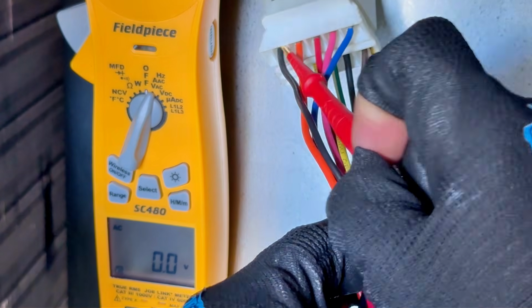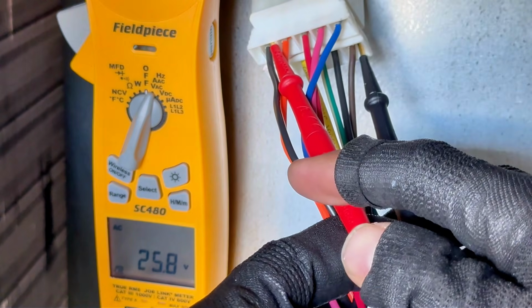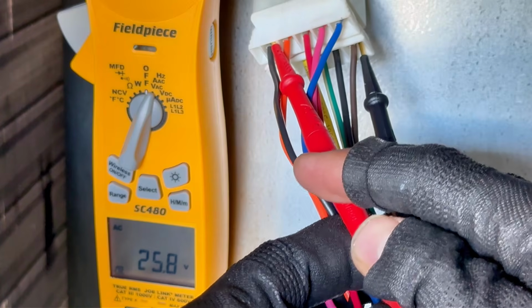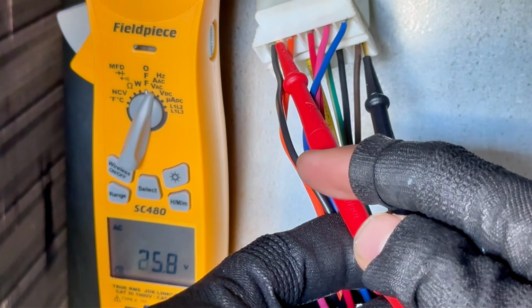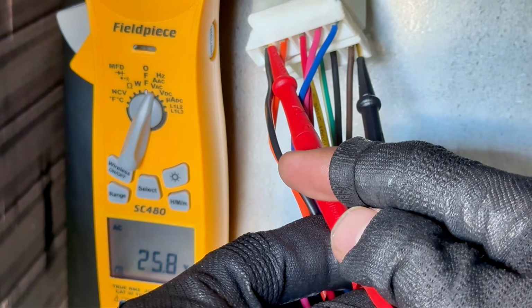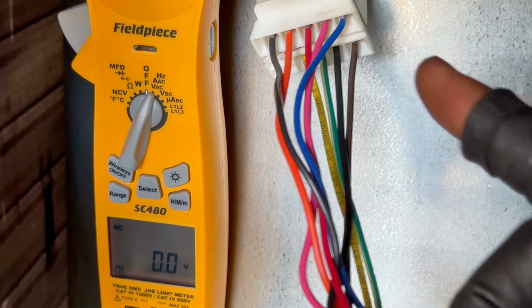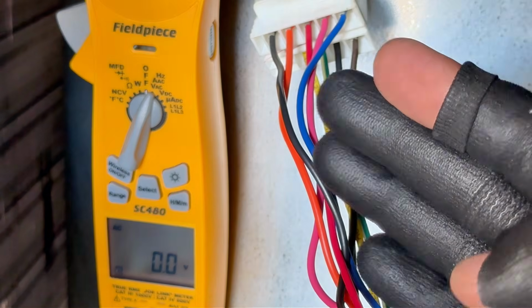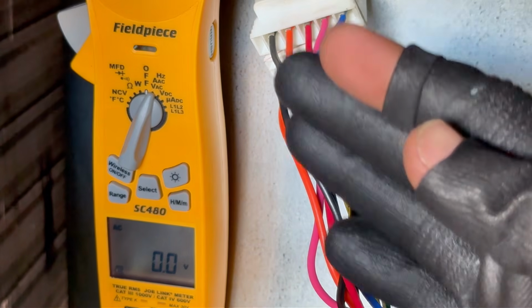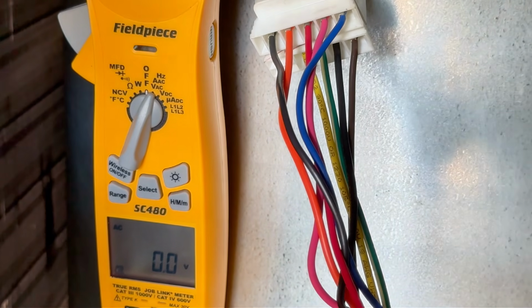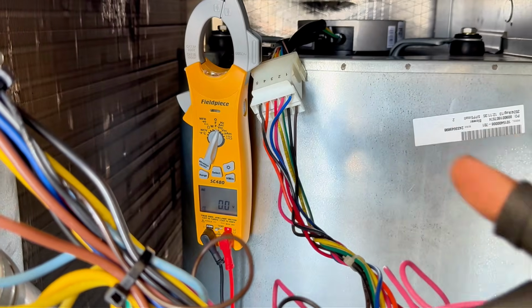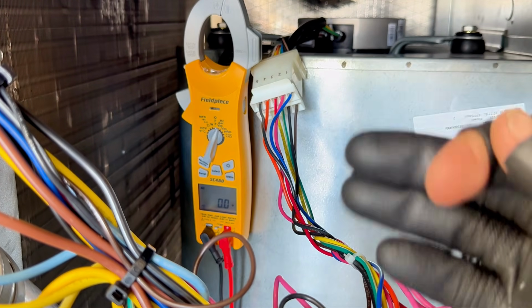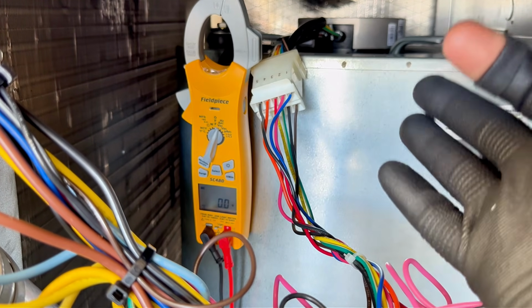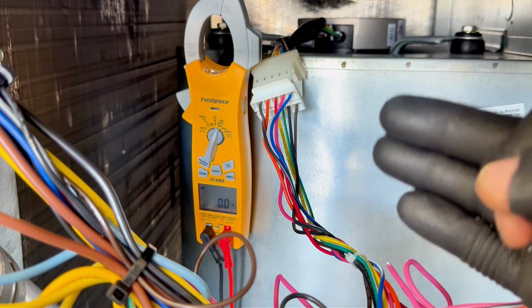I'm gonna go ahead and check that, okay? And you see, I'm getting about 24 volts, okay? And that's it. That's all you're doing for an ECM. You're checking if you have high voltage and low voltage when you call for cooling. And if you got voltage and that motor is not spinning, it's acting weird, it could be a bad module that went bad. Typically, it is the module on these that go bad.